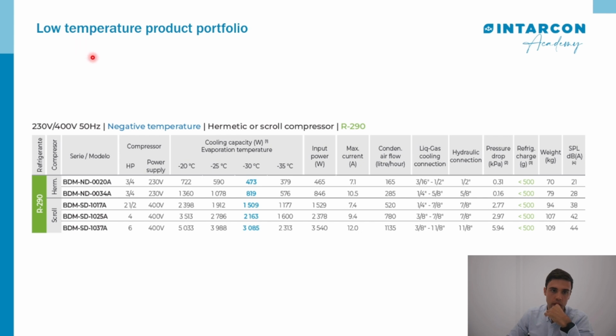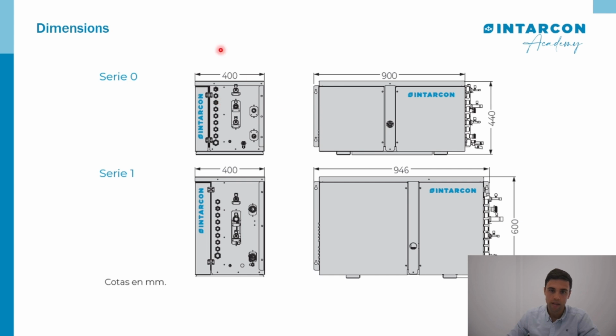Next, let's see the low temperature portfolio product. Let's continue with the same idea of using a reciprocating compressor in chassis 0 and a scroll compressor in chassis 1, with a compressor horsepower range between 3/4 and 6 horsepower. For a common application of evaporation temperature of -30 degrees, we obtain a cooling capacity range between 470 watts and 3 kilowatts. Also, we comply with the refrigerant charge that is lower than 500 grams. Dimensions: let's see this equipment for Series 0 and Series 1.